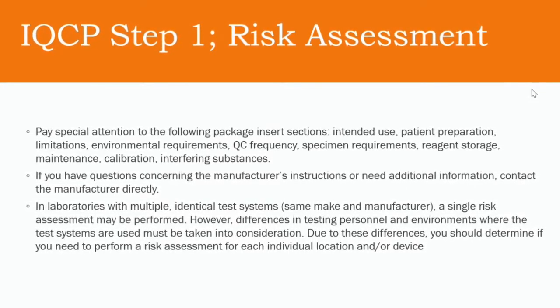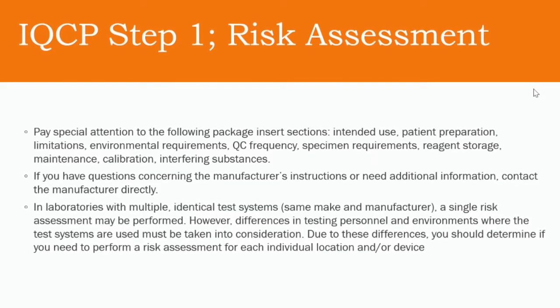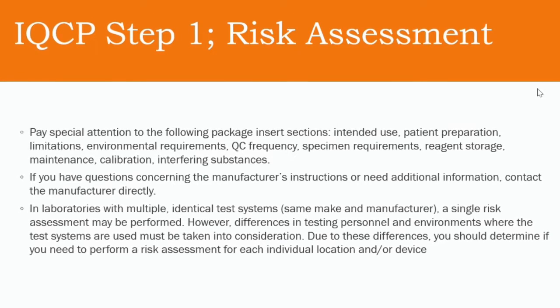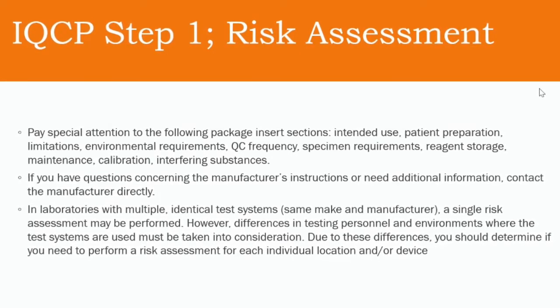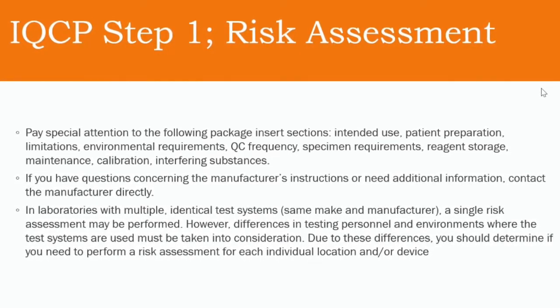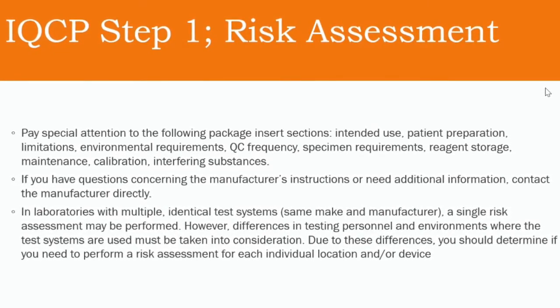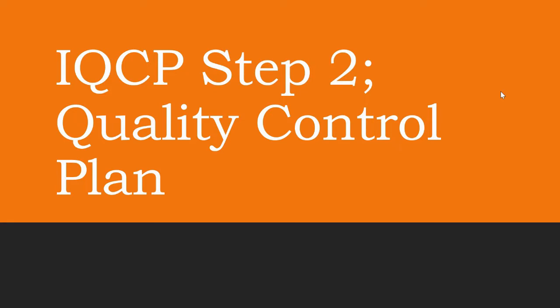However, differences in testing personnel and environments where the test systems are used must be taken into consideration. Due to these differences, you should determine if you need to perform a risk assessment for each individual location and device. Next comes the plan that the laboratory will adopt to perform QC testing.